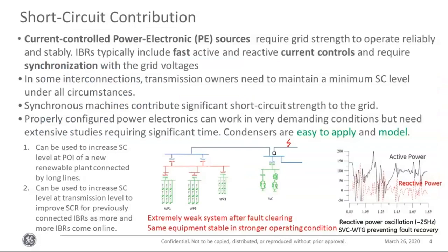The first helpful feature of synchronous condensers is short circuit contribution. Now, as we have more and more IBRs that are located far away, connected by long transmission lines, and that have very limited short circuit current contributions, the strength of the grid reduces. But a lot of these IBRs, which are current-controlled grid-following, do need the grid strength to be able to operate reliably, because they rely on being able to latch on to the grid voltage angle so that the current can be injected at the proper phase. Additionally, you have these fast active and reactive current controllers, and the current controls might become oscillatory, especially if your controls are faster than the system dynamics.